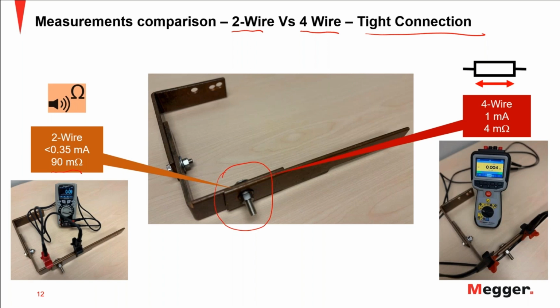And then here we have the four-wire method using 1 milliamp, very low current still, but we are getting 4 milliohms as a result. So you can see here that it's an 86 milliohms difference, 183% difference between the two measurements. So if you just want to verify continuity, yes, but what is the quality of that continuity? You're not going to see it with a continuity measurement. You need to use the four-wire method to know if you really have a low resistance. And we're going to talk about why it is important to be sure that it has a good quality connection there.